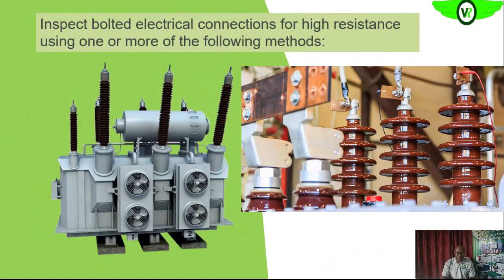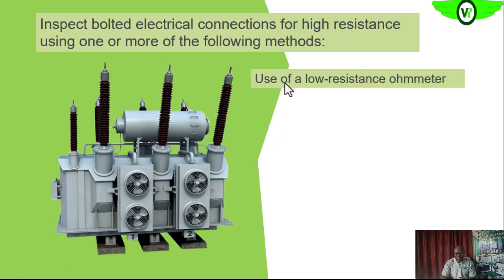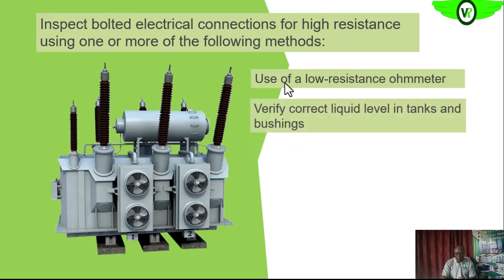So we want to also inspect all the bolted electrical connections for signs of high resistance. So those high resistance points, of course, we'll see the discoloration or deposits of metal oxides, those whitish substances or greenish substances. So if those are visible on those connection points, okay, those terminals, of course, we want to take the necessary action, clean and tighten properly. So we can also use the low resistance ohmmeter to check the level of resistance at those connection points.